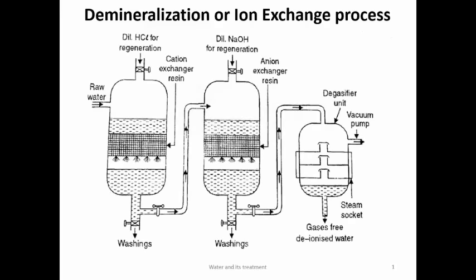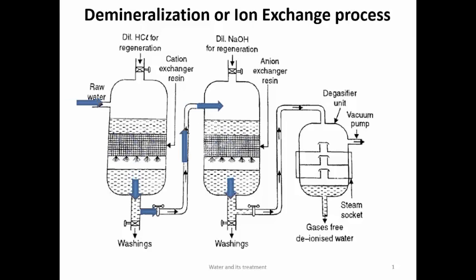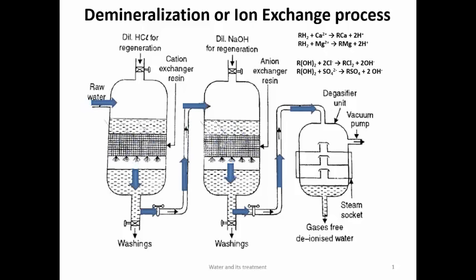In the diagram: raw water enters from the top inlet and percolates through the cation exchange resin, where H⁺ ions replace Ca²⁺ and Mg²⁺. The same water then percolates through the anion exchange resin, where SO₄²⁻ and Cl⁻ from hard water are replaced by OH⁻ ions. H⁺ from cation resin and OH⁻ from anion resin combine to form undissociated water molecules. The water still contains dissolved gases, so it passes through a degasification unit heated to ~80°C with vacuum evacuation, yielding gas-free deionized water.